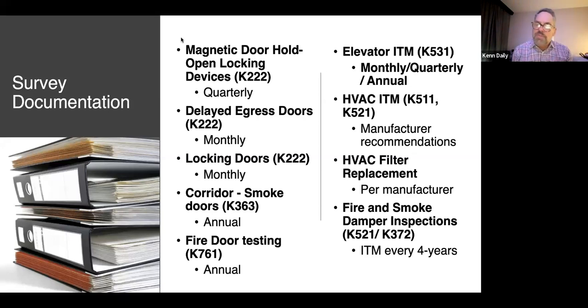And then corridor smoke doors, again, the construction of those doors has to be solid wood core doors, or 20-minute fire rated doors can substitute for that. They can be a little skinnier, but they have to close and latch. Again, latching is the critical element there. Then there's fire door testing. So doors in your building that are rated for fire doors that are going to be 45 minutes or 90 minutes, or in some cases, you may even have a 3-hour door. All those doors have to have an annual fire door inspection, which I believe is 11 required elements that have to pass a basic inspection.